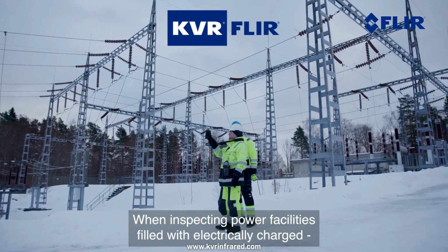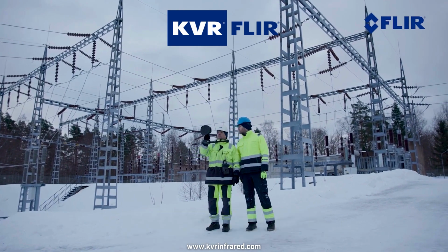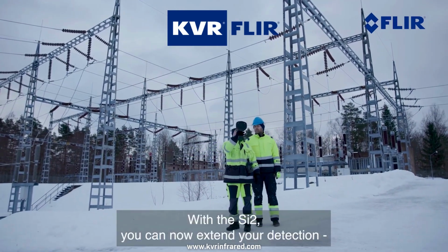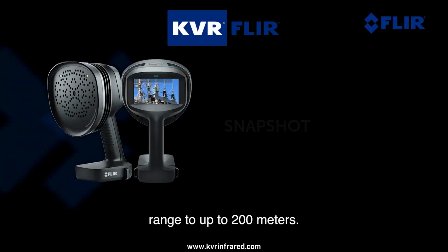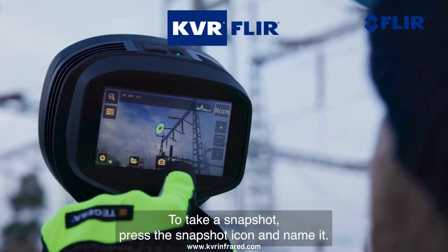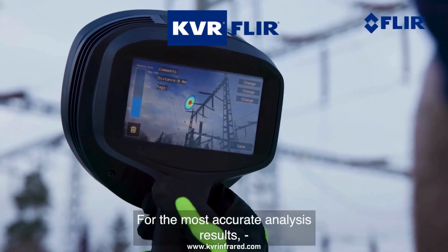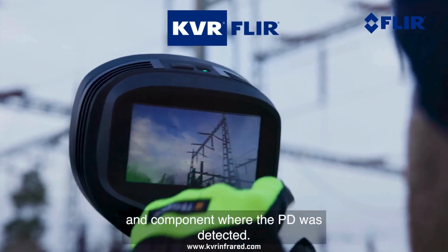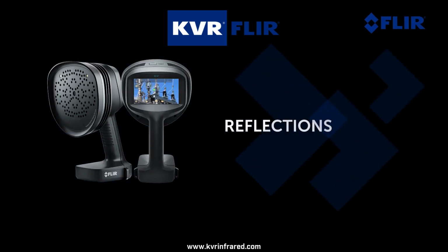When inspecting power facilities filled with electrically charged equipment, being able to detect PDs without contact and from a safe distance is key. With the Si2, you can now extend your detection range to up to 200 meters. To take a snapshot, press the snapshot icon and name it. For the most accurate analysis results, enter the approximate distance, voltage, and component where the PD was detected.